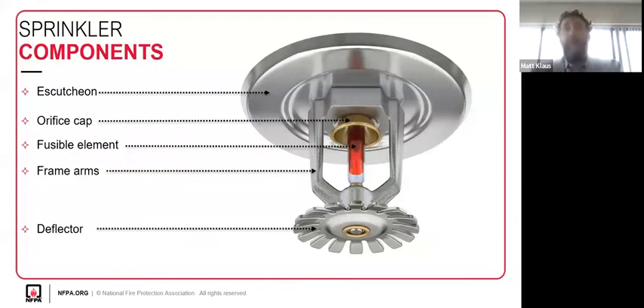It only happens where each individual sprinkler sees that activation temperature and the fluid can expand and break the bulb. So when we see in a Hollywood movie where 30 sprinklers go off at once, that's not a real phenomenon that happens all that often. You might have very extreme events where you see 20 devices open at the same time, but that's Hollywood.